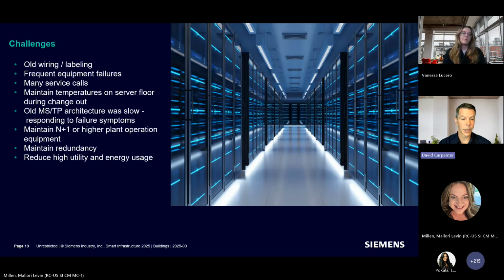With the change outs, we needed an N+1 in the mechanical cooling equipment as a minimum, to make sure there's an option for replacing a control panel or rewiring sensors and outputs, so a single piece of equipment can be turned off while we're working on it and still maintain the building. Of course, having denser redundancy than N+1 is ideal, so there can still be a lead-lag function operating during that change out. Minimizing the time it took to replace a single panel was important so we could get a panel back online and maintain the redundancy that NOVVA's customers expect from them.